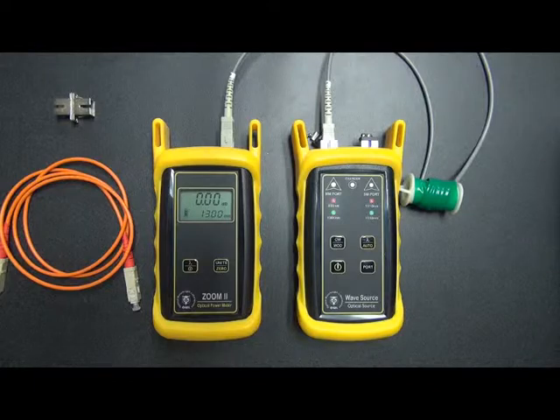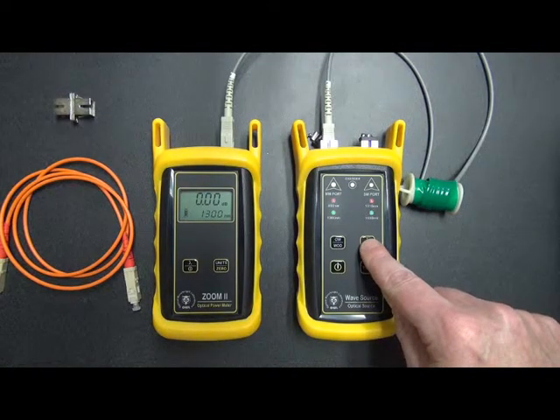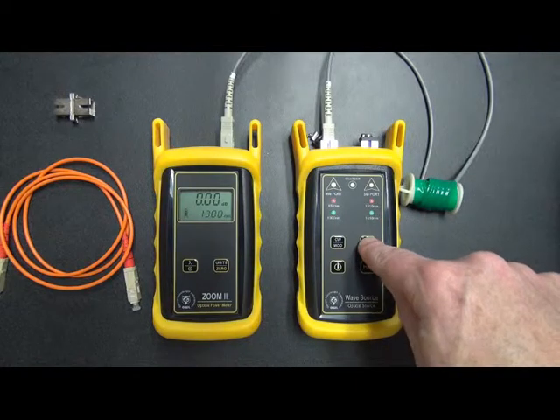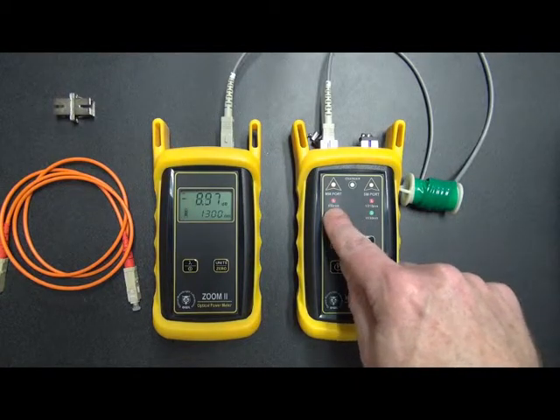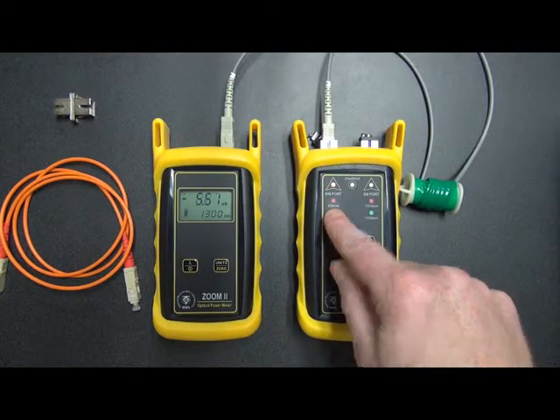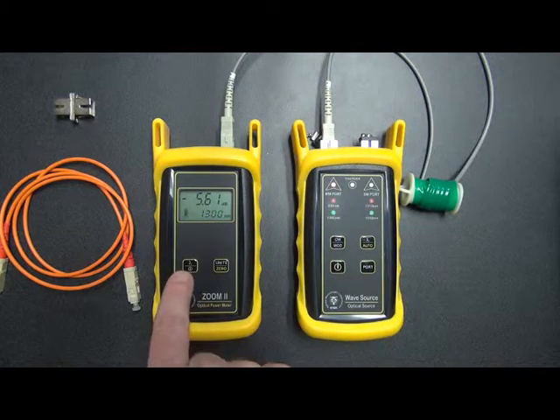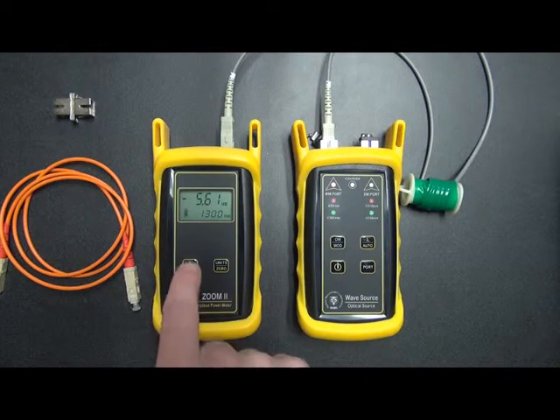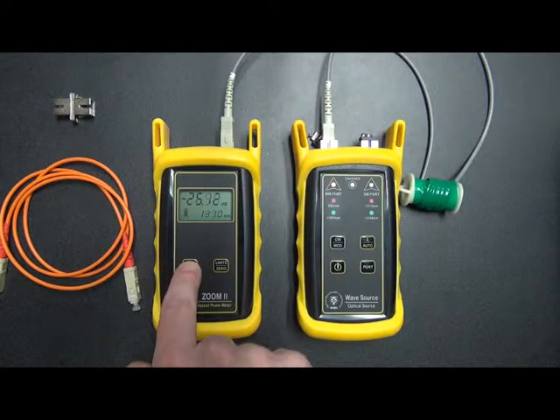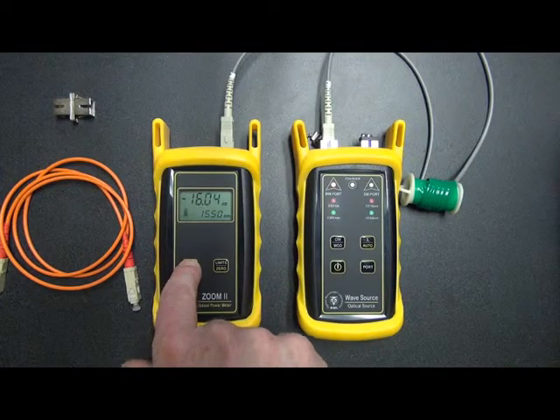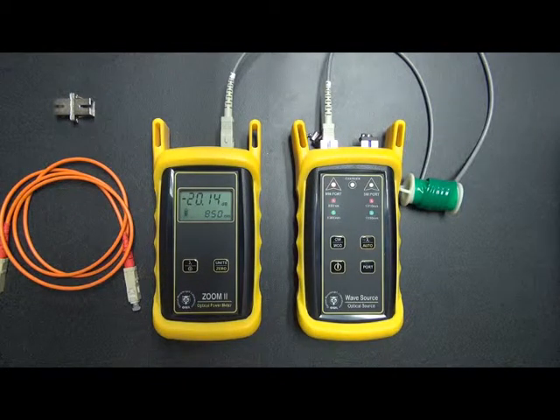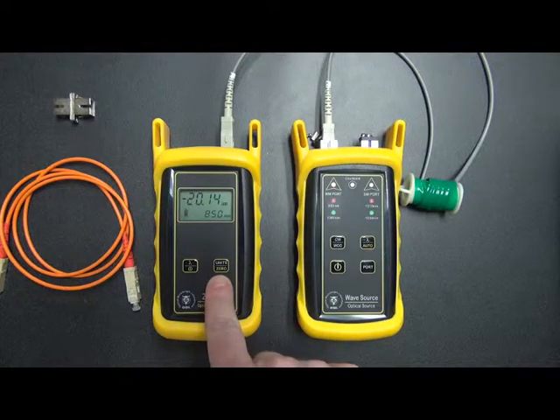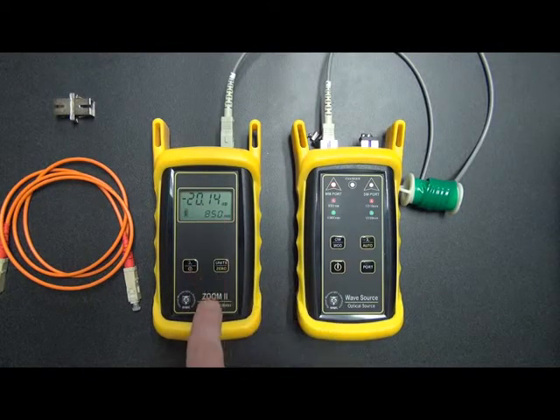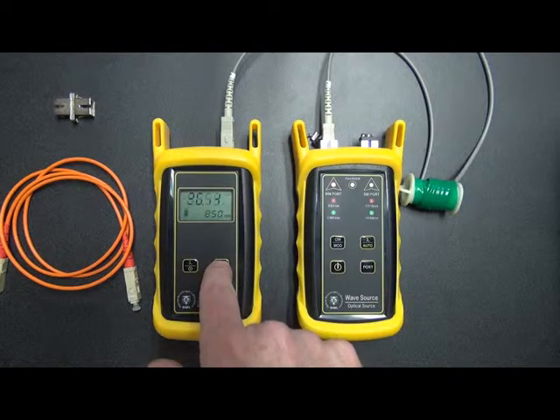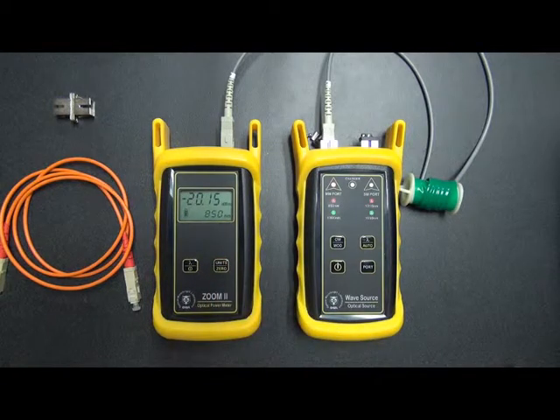But we also want to set the reference for 850, so we're going to press the wavelength button on the wave source. Again, it will switch back to red, or 850, and then we need to switch the wavelength to 850 on the meter. So we simply press the button until it reads 850 nanometers. And also, we want to make sure that we're reading in dBm mode. So we press the units button until we read dBm.